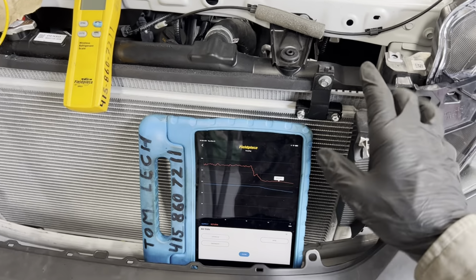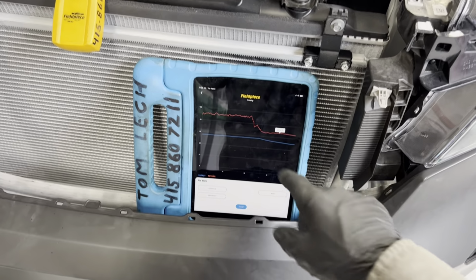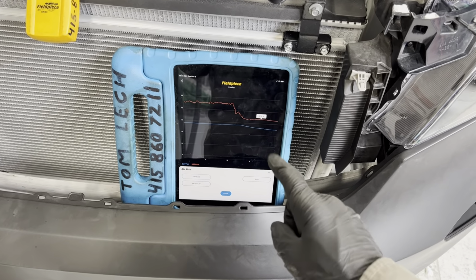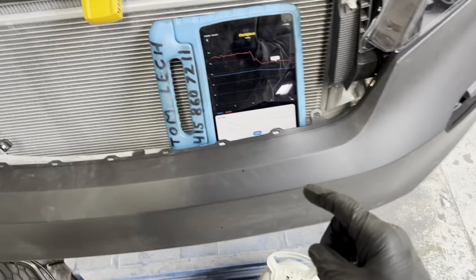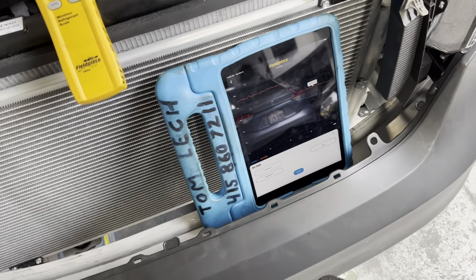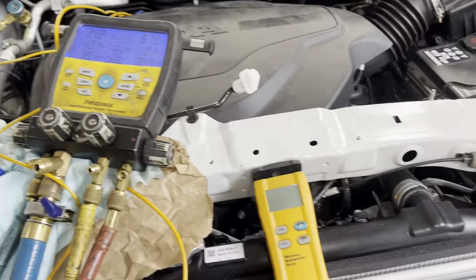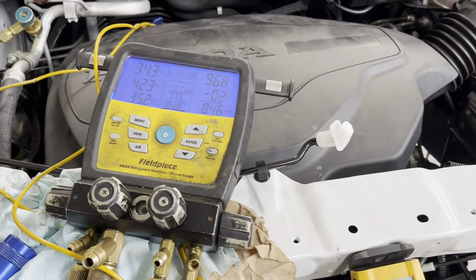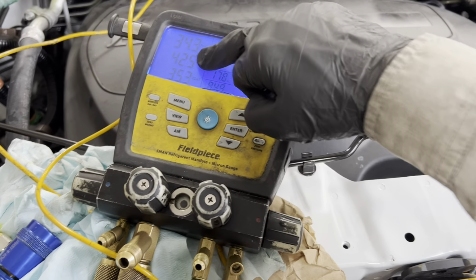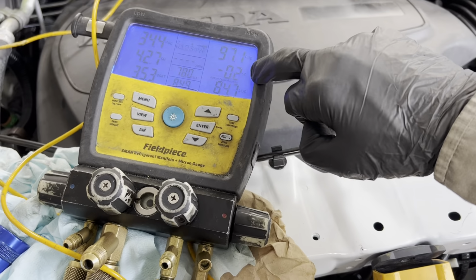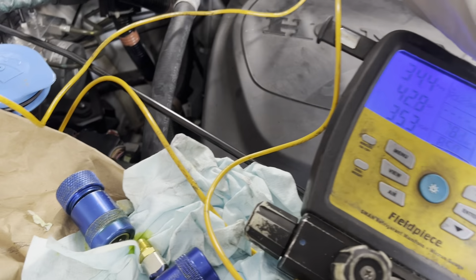I wonder if there's a- oh, this is too new, it probably doesn't have a TSB. But I'm gonna check if there's any TSBs on the air conditioning, see if they had any update on the refrigerant charge. Because to me, that looks like with that superheat and that subcooling, even when I had it over here, it was near zero.